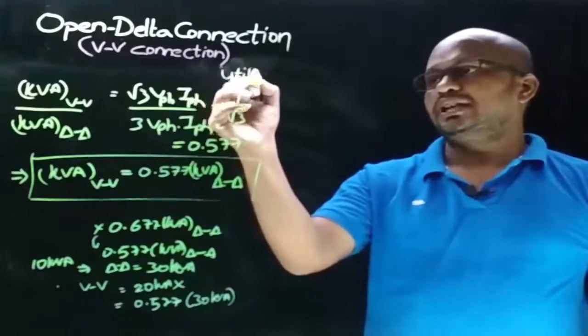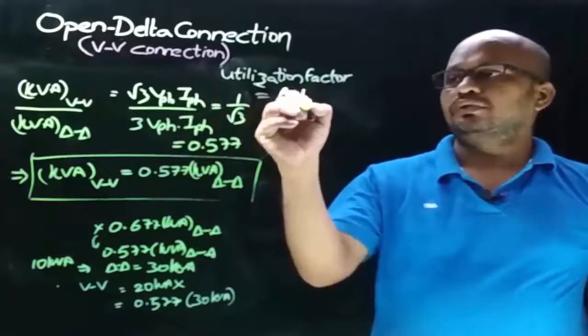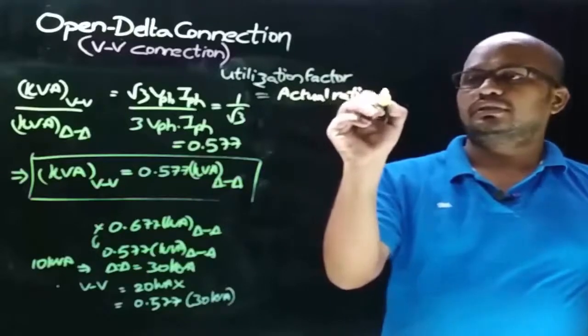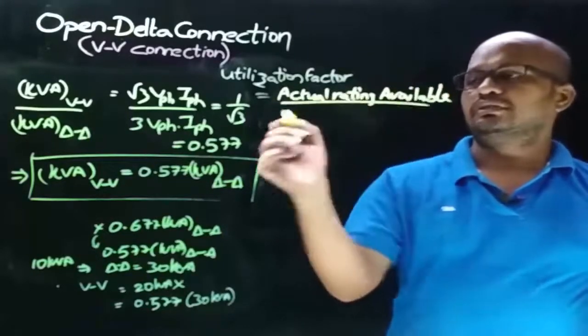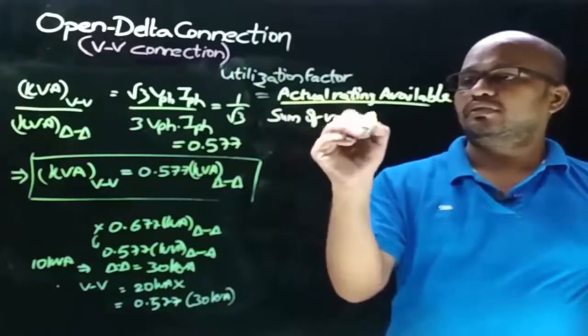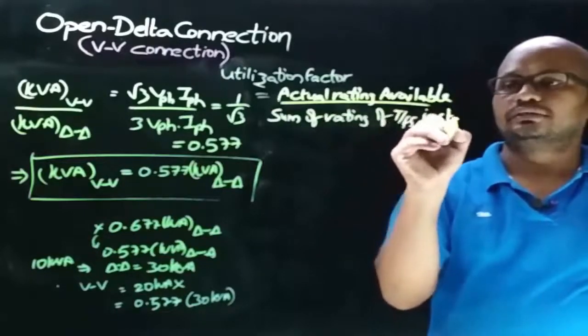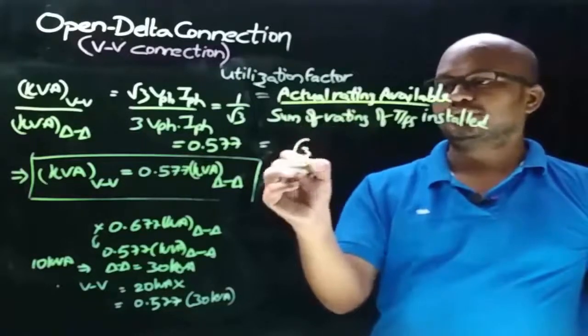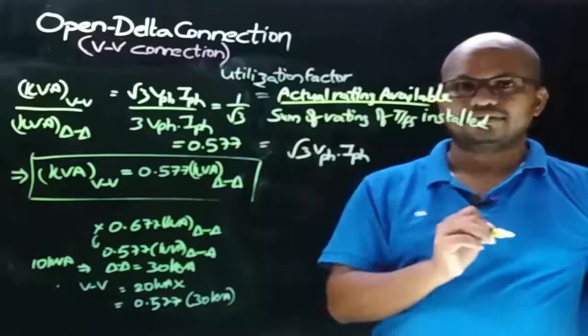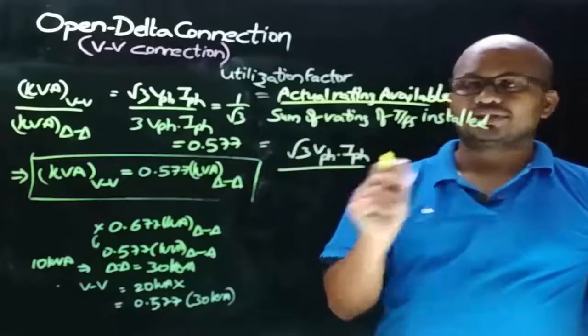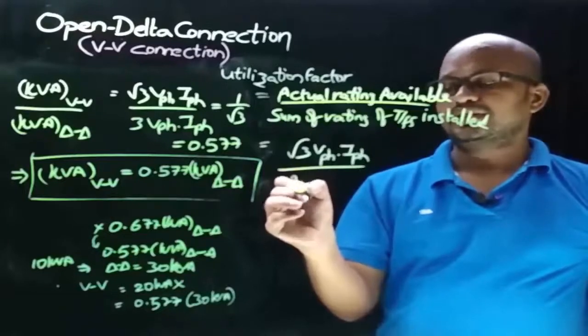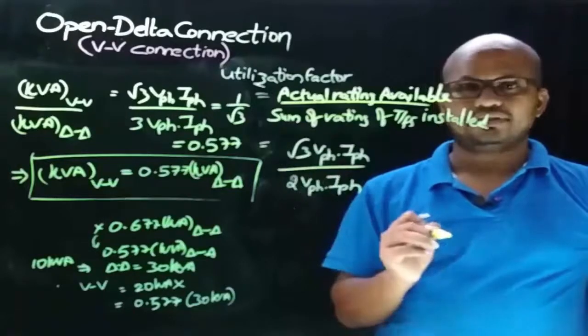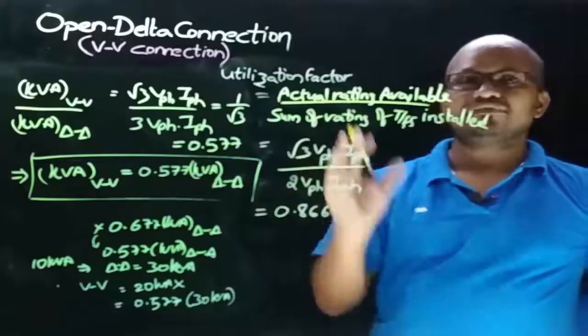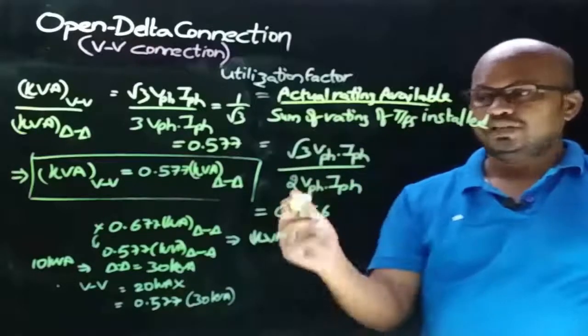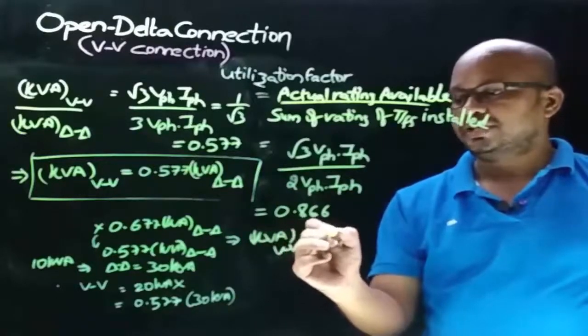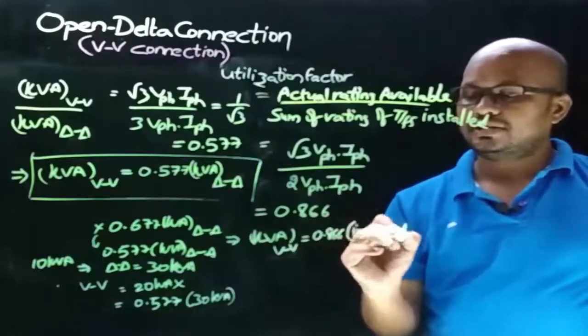Now let's find the utilization factor, which is equal to the ratio of the actual rating available to the sum of the rating of transformers installed. Therefore, the actual rating available in open delta connection is root 3 times V phase into I phase, to the sum of the rating of transformers installed. So the 2 transformers' rating sum is 2 times V phase into I phase, and that will give you 0.866, meaning the utilization factor for open delta connection is 0.866, which tells you that the power supplied by open delta connection is 0.866 times the installed capacity.